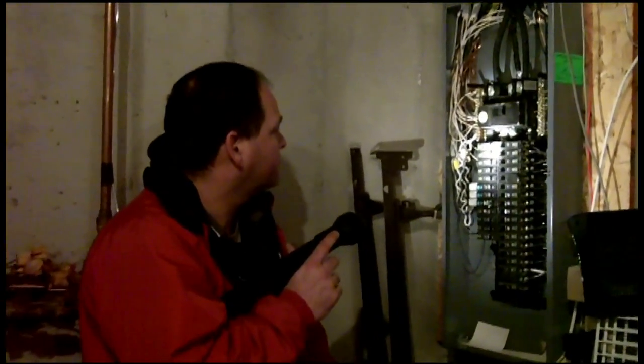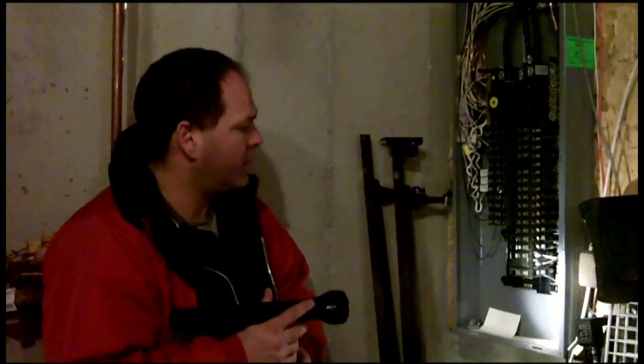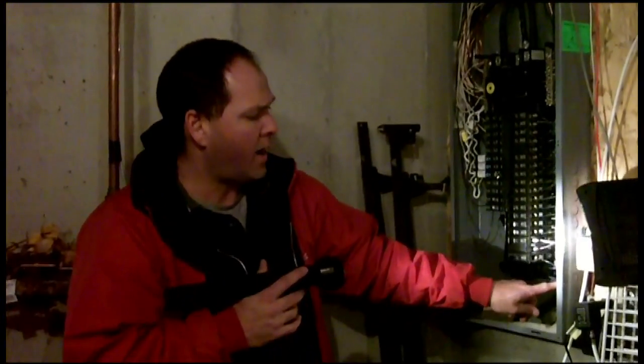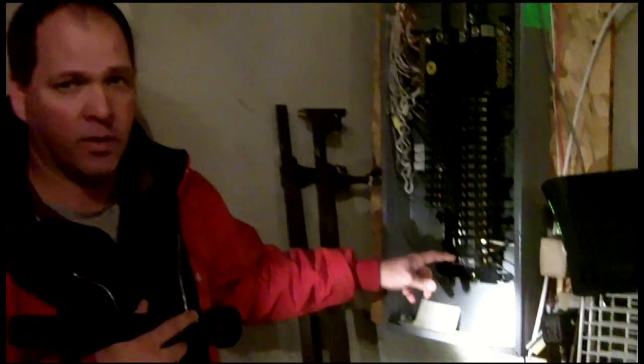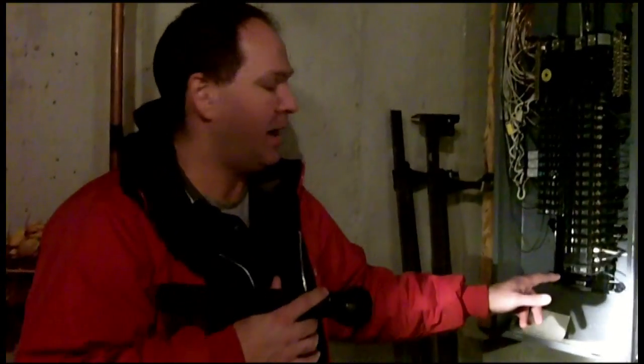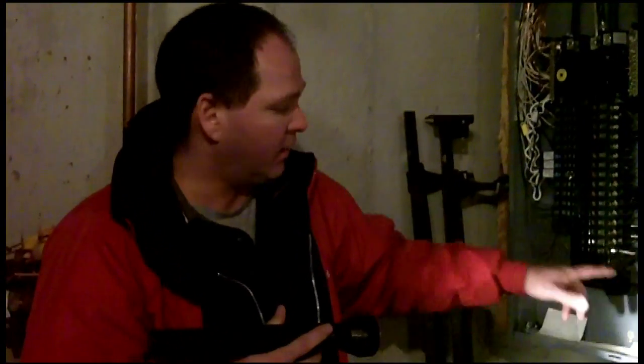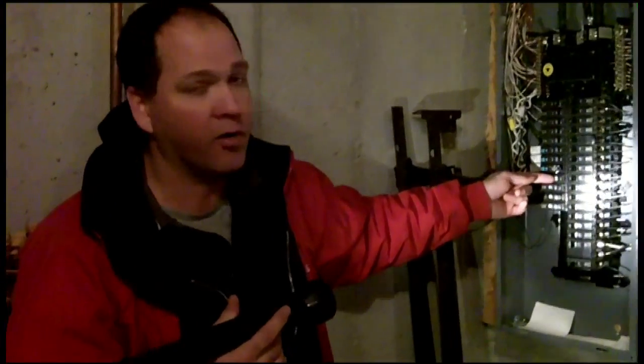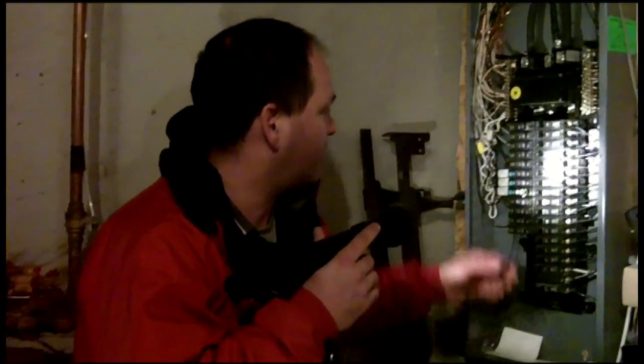So Joe, I see you've taken the electrical box apart—tell me what you're looking for in here. Mainly we're making sure the wires are compatible with the breakers. You have different size wires—14 gauge, 12 gauge, 10 gauge—and they're only rated for a certain amount of amps to come through. A 14 gauge wire, for example, is only rated to carry 15 amps, so I want to make sure it's not attached to a breaker larger than that. Otherwise it would have the ability to draw more power, which could overheat the wire and damage it. So we check that out here.